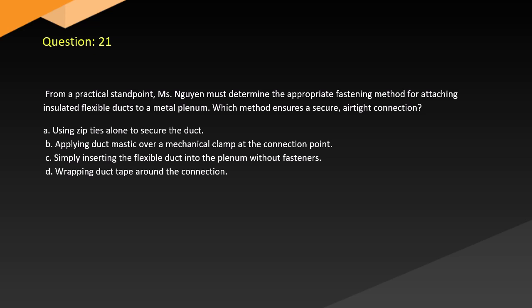Question 21. From a practical standpoint, the technician must determine the appropriate fastening method for attaching insulated flexible ducts to a metal plenum. Which method ensures a secure airtight connection? A. Using zip ties alone to secure the duct. B. Applying duct mastic over a mechanical clamp at the connection point. C. Simply inserting the flexible duct into the plenum without fasteners. D. Wrapping duct tape around the connection.